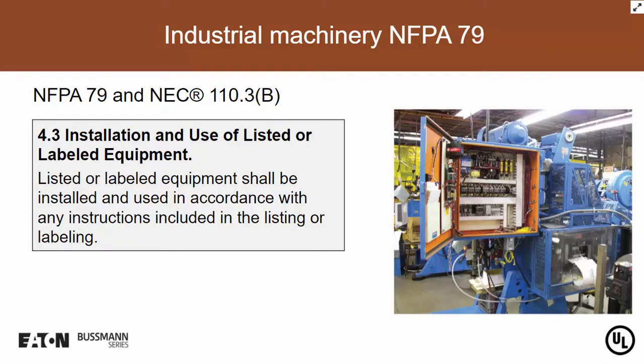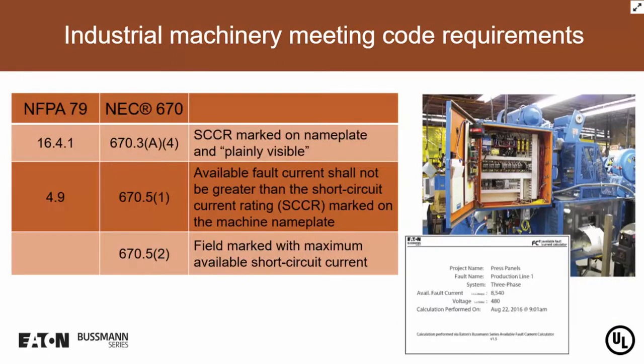Because I can tell you, as a member of UL staff, when we evaluate products, we certainly not only evaluate the product itself, but we evaluate the material supplied with it, the printed material. And it comes in many different forms. It could be just simply labels. It could be an instruction manual. It could be paper that's considered a stuffer sheet put into the packing container that the product is shipped in. All that material is really part of the listing. So it's very important to make certain that it's read and understood, and if there are any instructions that need to be followed in order to ensure proper installation of the product, those instructions must be followed in order to ensure a code-compliant installation.